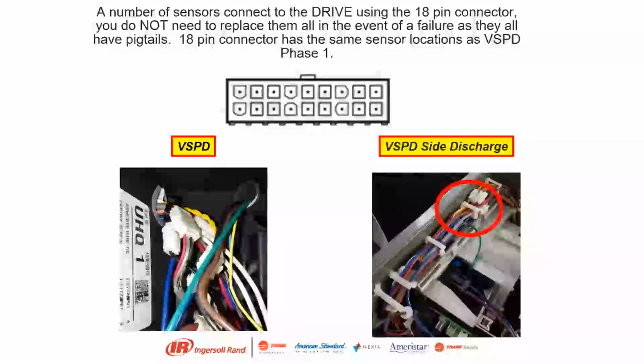Number of sensors connected to the drive using the 18-pin connector. Now in the service facts, I'm going to go through it because this is important. There's only 5 sensors in these units. In the Link, there's going to be 7, but there's only 5 sensors in here. Once you get fluent with checking sensors, it's no issue, and you can rule out a lot of information pretty quick. And we're going to ask you to do it.